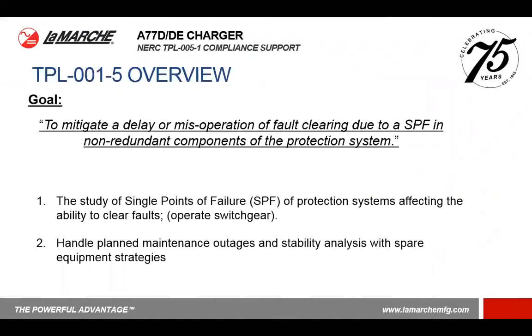As an overview, TPL-001-5's goal is to mitigate a delay or misoperation of fault clearing and the single point failure of non-redundant components in a protection system. Essentially, this breaks down into 2 parts. The study of single points of failure of a protection system that could affect the ability to clear faults. Think of that as the ability to operate switchgear. And you must also be able to handle planned maintenance outages and run a stability analysis with spare equipment strategies.